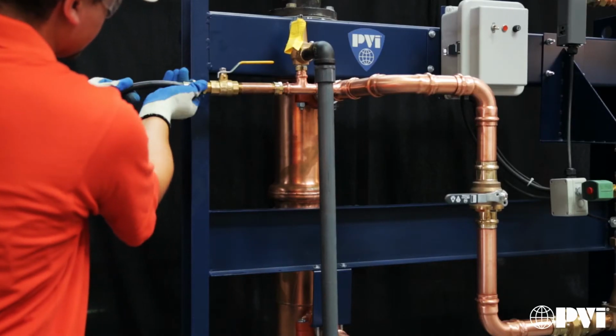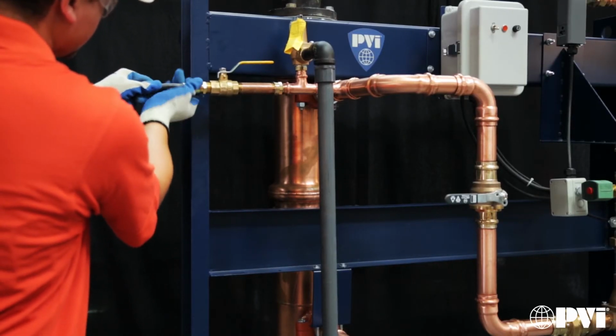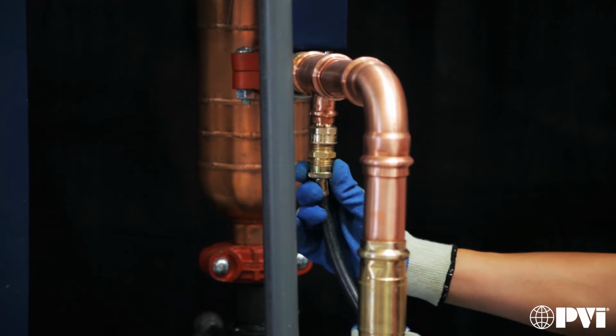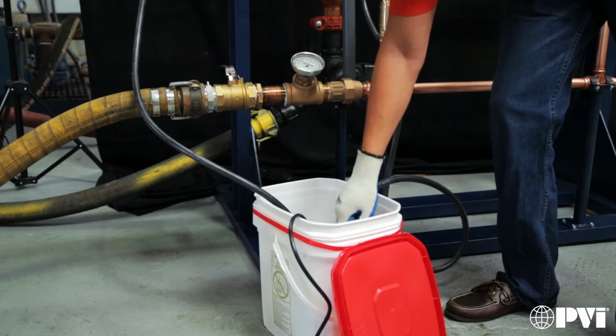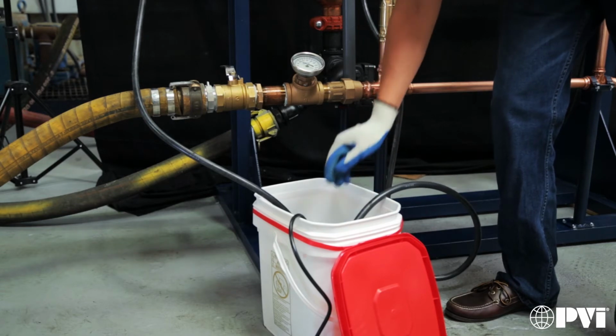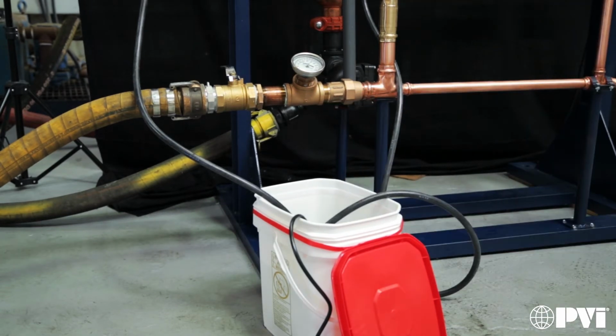Feed the plastic tubing into the top clean-in-place fitting and into the heat exchanger and secure. Place the pump in the bucket, careful not to splash. The cleaning solution will be acidic in nature. The acid solution will become neutral in pH as it cleans the heat exchanger surfaces. The objective of the cleaning process is to have the cleaning solution remain at or near its initial acidic pH, where no dissolving of scale is taking place and the heating surfaces are clean.